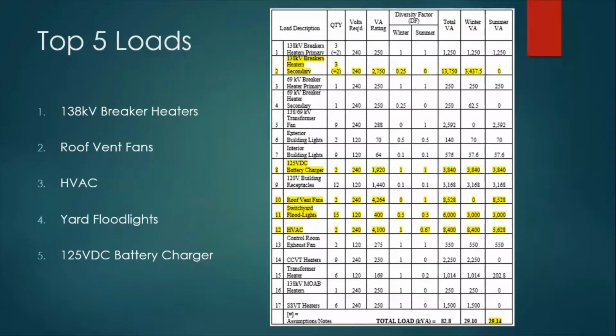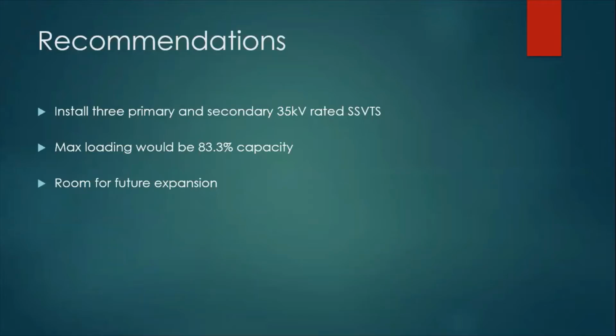Demand factors, which are a measure of how often the load will be expected to run, were considered for the seasons of winter and summer. Loads such as transformer fans have a demand factor of 1 in the summer to maintain operating temperature, but are reduced to a factor of 0 in the winter when sub-zero days are common. The top 5 loads that affected the total demand include breaker heaters, roof vent fans, HVAC, yard floodlights, and the 125-volt DC battery charger that was selected in conjunction with the DC battery study to charge at the recommended rate. Under the worst case loading conditions, summer would be the limiting factor at 29 kVA. Therefore, each recommended SSVT is rated for 35 kVA, which accounts for 83% of maximum capacity.